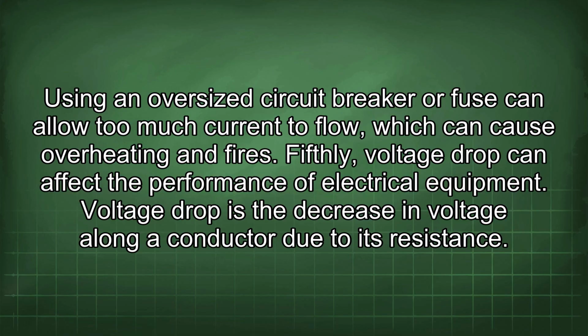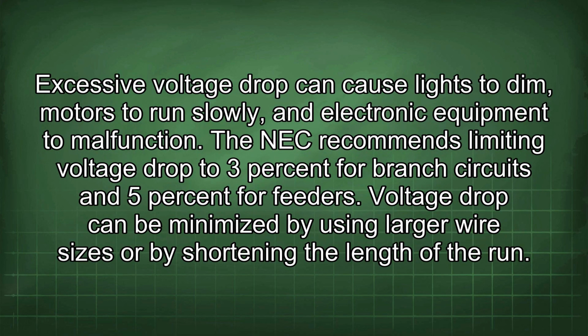Fifthly, voltage drop can affect the performance of electrical equipment. Voltage drop is the decrease in voltage along a conductor due to its resistance. Excessive voltage drop can cause lights to dim, motors to run slowly, and electronic equipment to malfunction. The NEC recommends limiting voltage drop to 3% for branch circuits and 5% for feeders. Voltage drop can be minimized by using larger wire sizes or by shortening the length of the run.